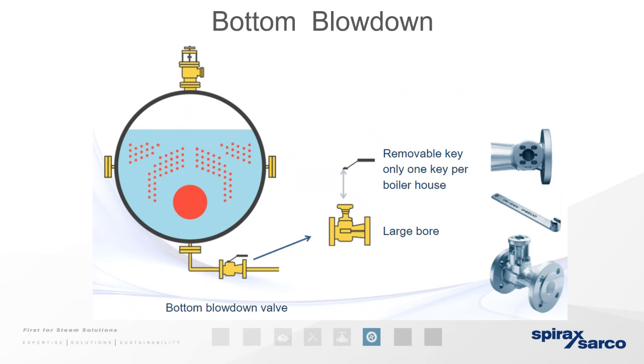Many of you, I've been to many boiler houses, and quite often you see more than one key. The reason why we sell a blowdown valve which has a removable key is we recommend there should only be one in each boiler house. So if you have 4 boilers, there should still only be one key. The reason being that prevents all 4 boilers from being blown down at the same time. So it's a manual mechanical mechanism for you to protect your system by only having one key. Only one valve can be operated at a time. These are also set on springs, so you physically have to push the key down and turn it to be able to hold down the blowdown valve. That means that the key can't stay in there.